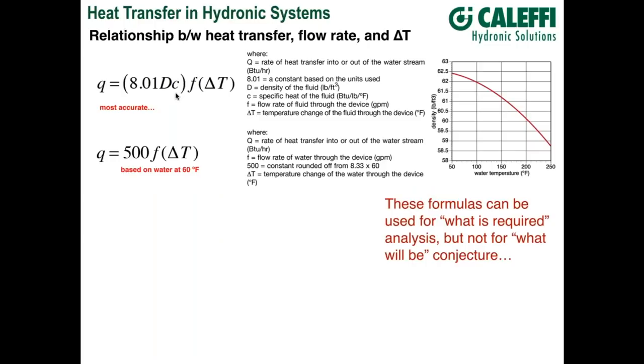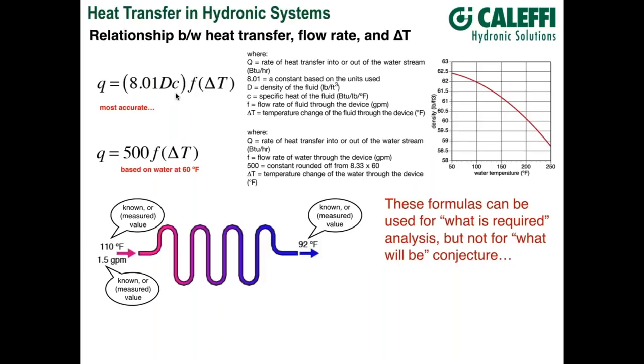What do I mean? Mathematically, we can play all kinds of tricks — we could make delta T a thousand and make the flow rate very small and get a given rate of heat transfer. The math keeps working, but the physics doesn't. For example, given a radiant panel circuit with 110°F water and a measured flow of 1.5 GPM with an outlet temperature of 92°F, we can put those measured values into the formula and calculate that the circuit is dissipating 13,400 BTUs per hour.